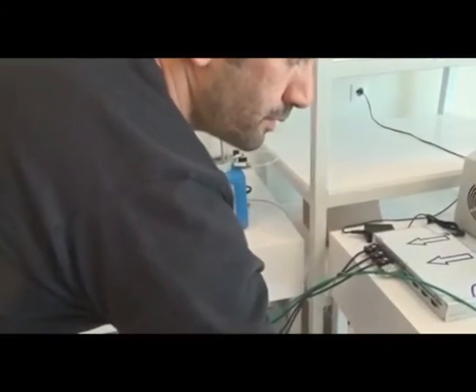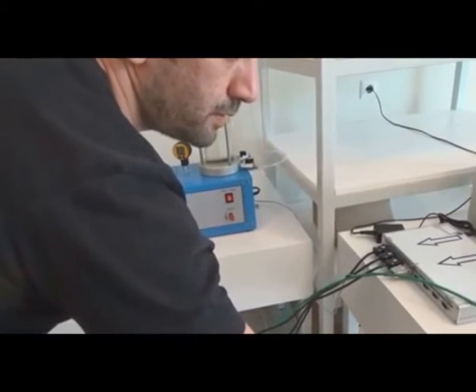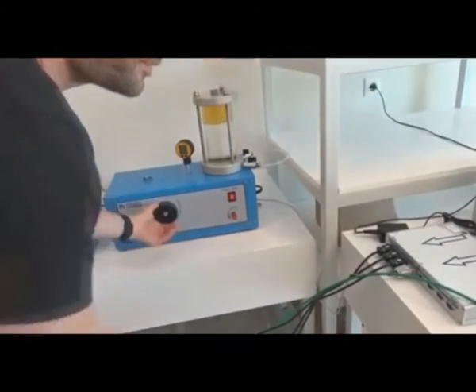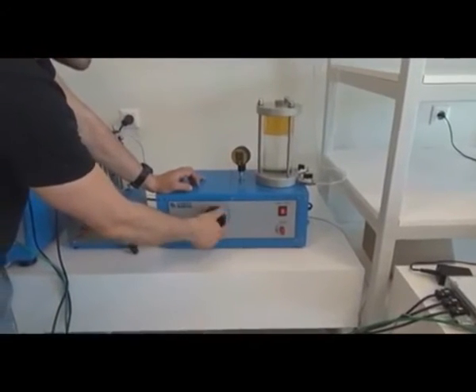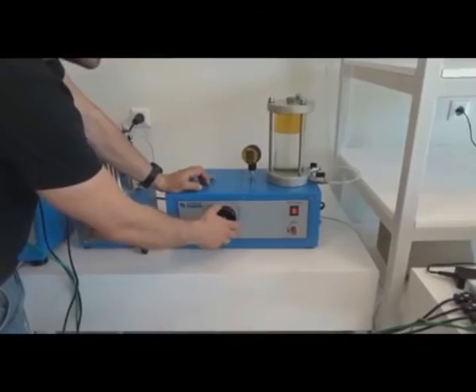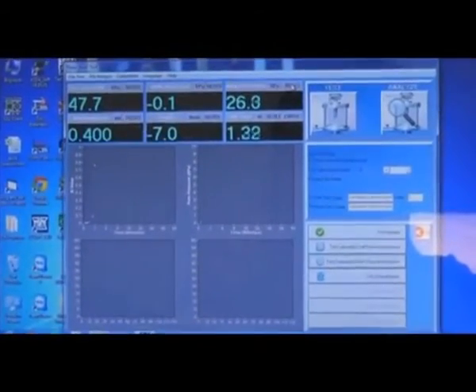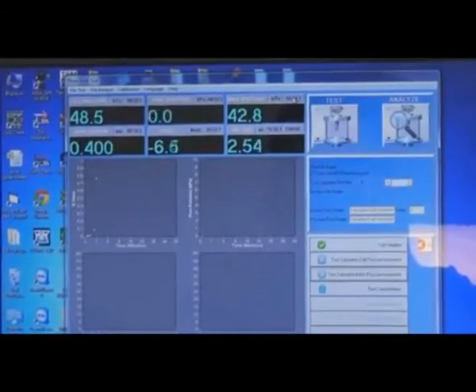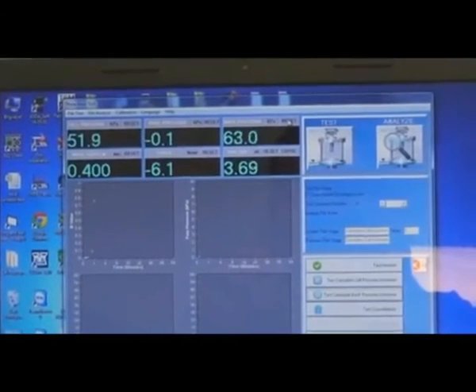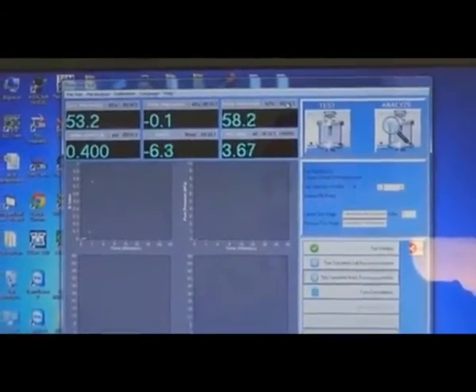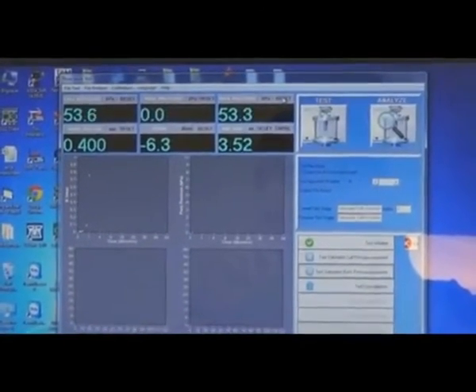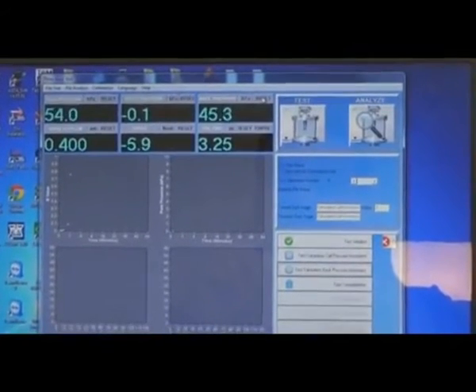Now, as you can see from here, as I move this knob and increase the pressure, the back pressure on the computer screen is going to increase. For example, we have exceeded the 40 kilopascals on the back pressure side over here, but since we didn't open the inner valve, we are on the safe side. We are now reducing the pressure to around 40 kilopascals.